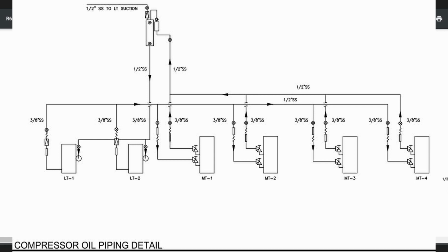And then we put our standard oil equalizing system. This is the same oil equalizing system we use on all our direct drive systems. And it's really quite simple. We pump oil from the low stage compressor's oil pump into a common line through a cap tube, and we pump then into the crankcase of the 4 medium temp compressors through another cap tube, which we've sized properly. We figured out how to size them. So there's no floats, there's no nothing on those. We're just always pumping oil from the low stage compressors to the medium temp compressors.